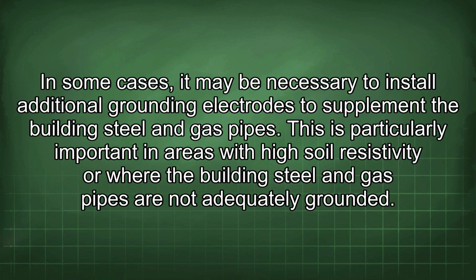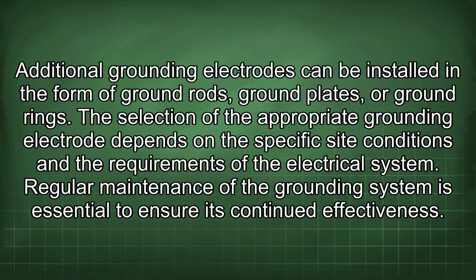In some cases, it may be necessary to install additional grounding electrodes to supplement the building steel and gas pipes. This is particularly important in areas with high soil resistivity or where the building steel and gas pipes are not adequately grounded. Additional grounding electrodes can be installed in the form of ground rods, ground plates, or ground rings. The selection of the appropriate grounding electrode depends on the specific site conditions and the requirements of the electrical system.